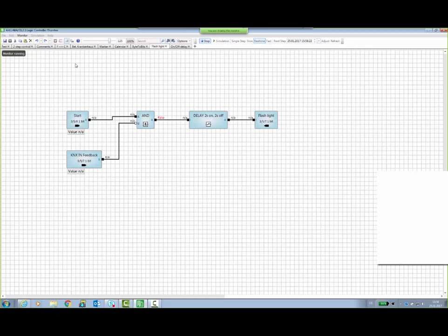Now Jürgen press now the button to start here. So send a group address 358. And you see now here, the relay is clicking on off and you see the output flashlight. True false means on off. So you see everything running here also inside the logic. And if Jürgen stops now, false is an off signal. And also the output is false means off. So it's a monitoring of all the functions in your logic and together with the communication on the bus.